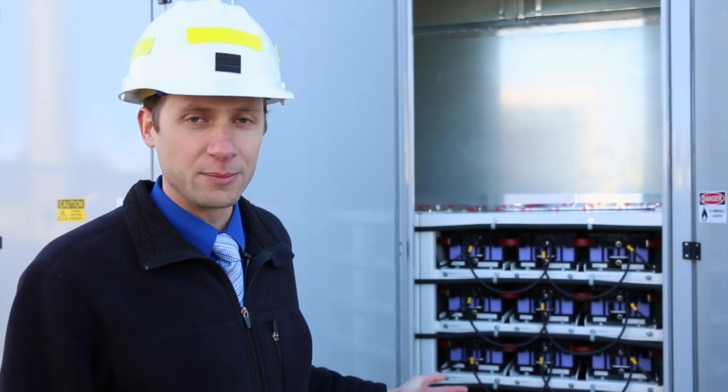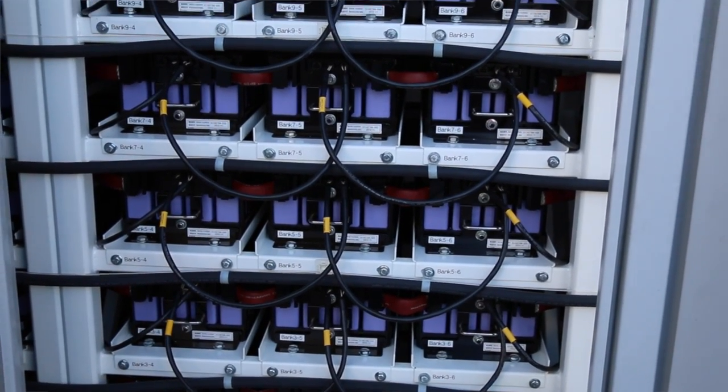We are now inside Hardison substation looking at the battery container. You can see the battery modules behind me. These battery modules were provided by Mitsubishi GS Yuasa. There's a total of 240 battery modules in the whole container — 12 different strings containing 20 modules in each string.